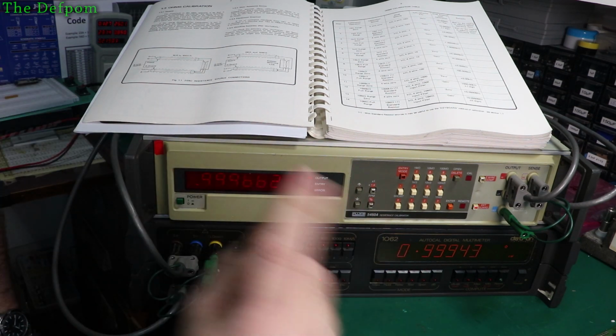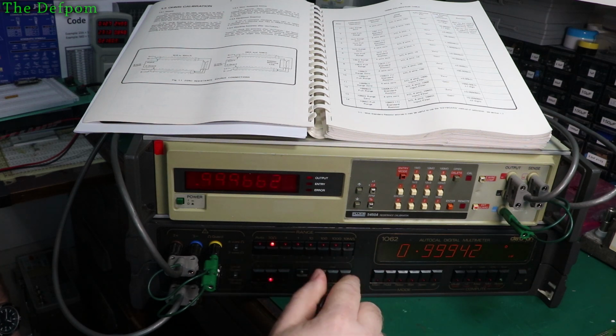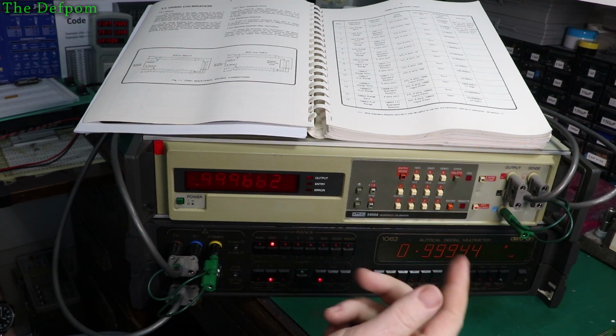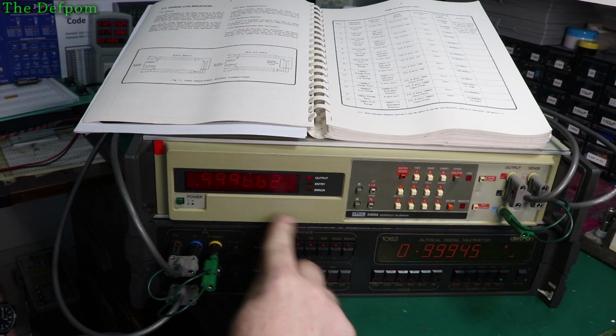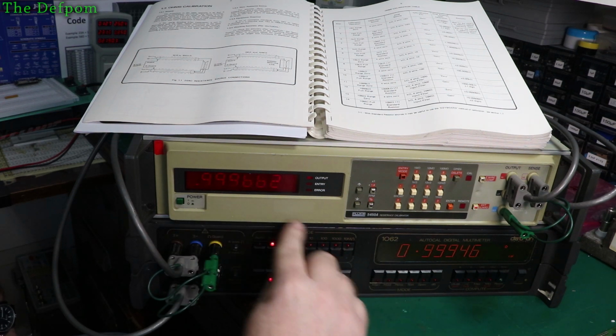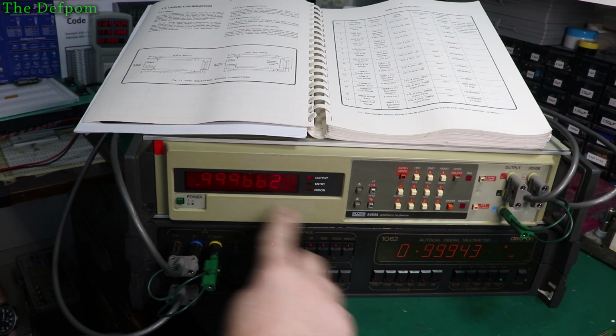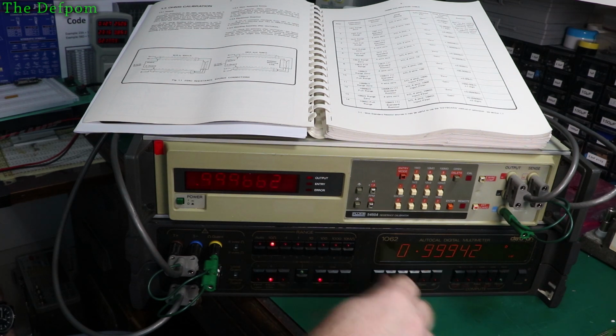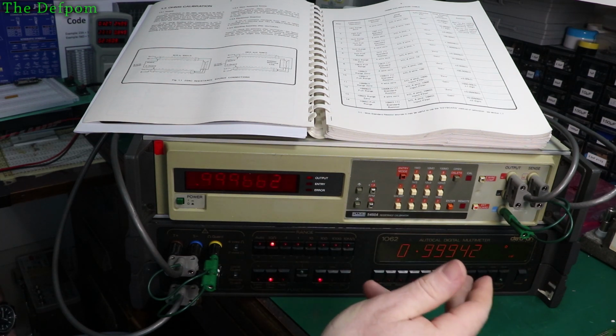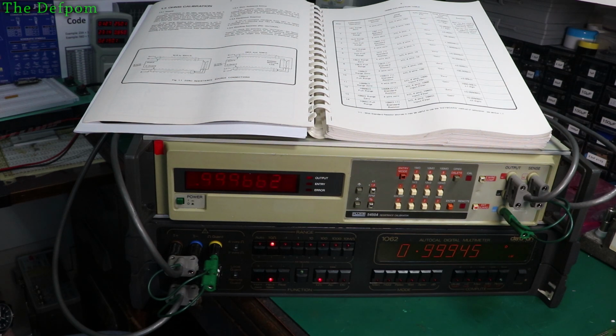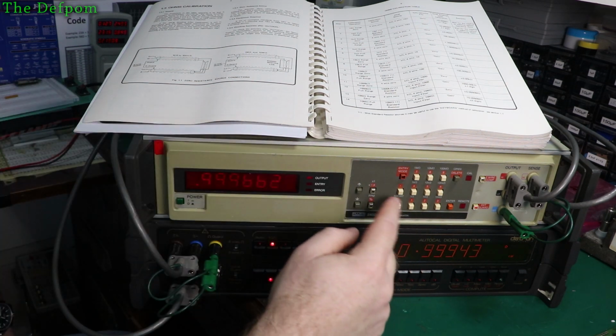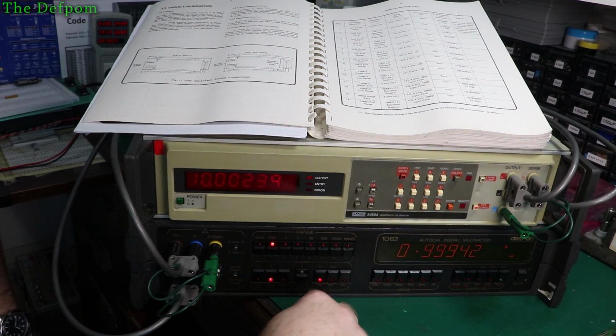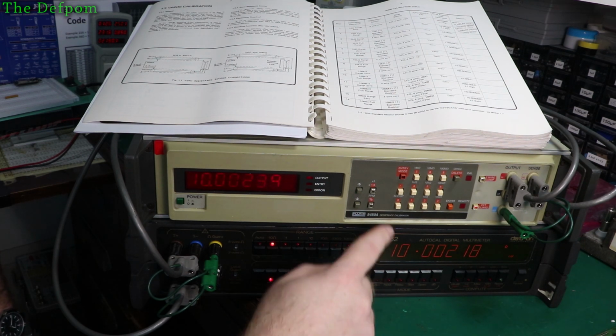So yeah, I'm pretty confident it's a linearity issue. I just did the 10 ohms range at 19 ohms, did that calibration. And if I'm looking at 1 ohm, it's supposed to be 99966 and I'm getting 99943. So yes, it's out by that 20 count still. I'm not quite sure how I can solve this problem. I'm going to have to look into it some more. If I go back to 10 ohms, that's about 20 counts down.